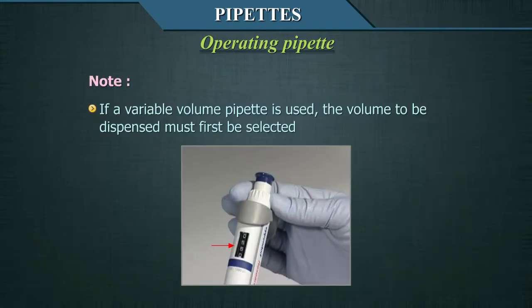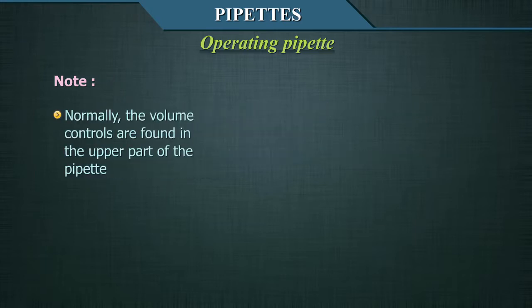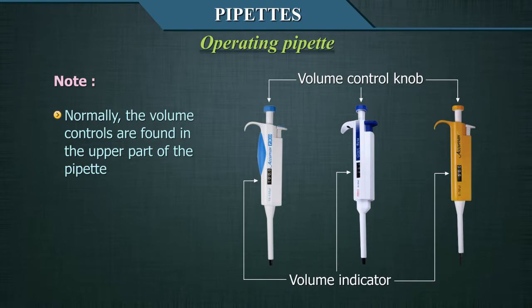Please note: if a variable volume pipette is used, the volume to be dispensed must first be selected by following the instructions indicated by the manufacturer. Normally, the volume controls are found in the upper part of the pipette, and it is necessary that the operator understands and learns to differentiate the scales.